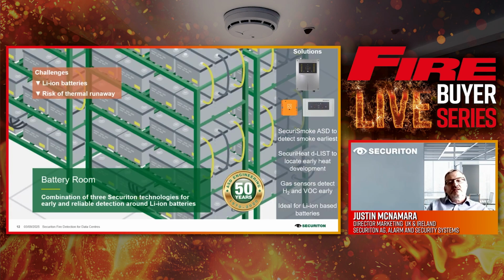There are other challenges becoming increasingly common. Battery rooms within data centers typically used sealed lead acid batteries, but it's much more common these days for new data centers, and even retrofits, to use lithium-ion batteries, which present a risk of thermal runaway. There's a lot in the news and press about the potential dangers of lithium-ion batteries. Manufacturing is certainly improving, but there's no way we can guarantee 100% safety, and it's a risk we need to address.